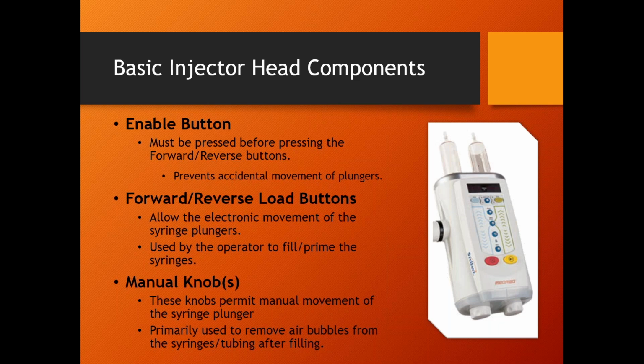Before these forward and reverse buttons work, you have to hit the move piston button. You hit it, and you have about 5 seconds to start moving the piston up and down. It's a safety thing, obviously. If the patient is connected to the injector, and we go to tilt it, and we hit one of these buttons, and all of a sudden we're shoving fluid in the patient before we're ready, it can cause problems. So that's why the move piston button has to be hit before these buttons are live and active. Once the piston stops moving, after about 5 seconds, the move piston button disables itself.